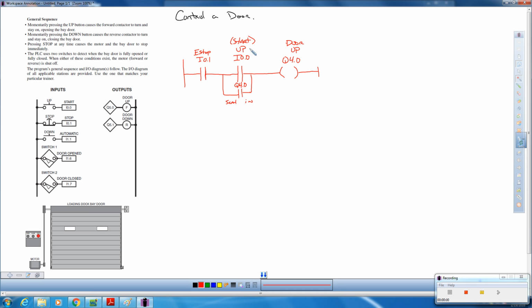Okay, that means that the second we hit the up button, when the e-stop's going already, this is energized, which energizes this switch. So as long as this guy stays energized, we're going to get the signal through here, because we closed this contact because it was momentarily started. This contact's not going to open back up when we let go of the up. This is why we have an OR here. So this is our seal-in. Even if the up has been released and it's open now, this guy's still closed because it was originally charged, so the path is now this way through our ladder.